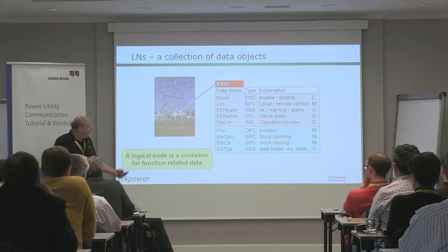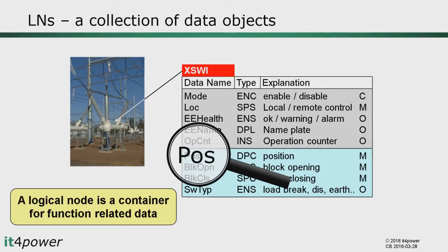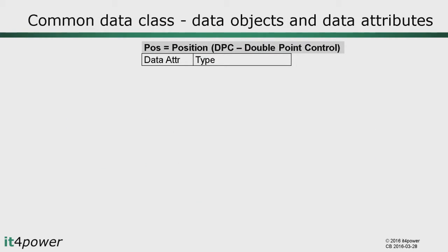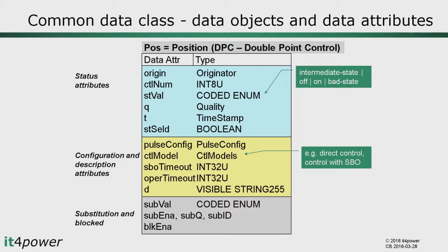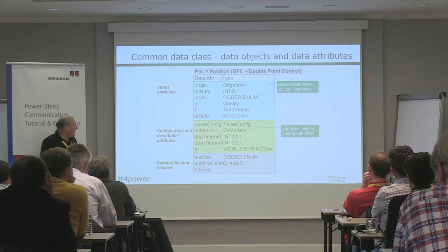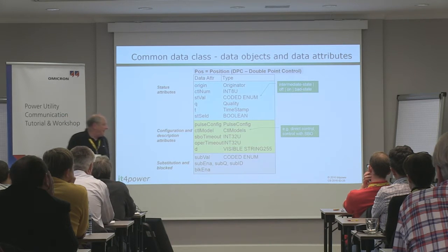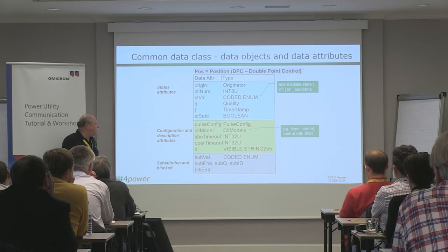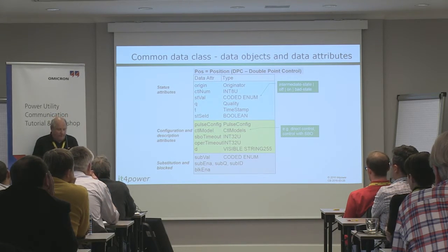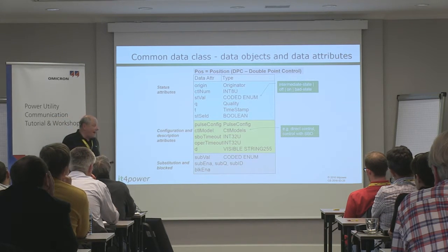Looking in more detail at the position data object, the common data class 'double point controllable' defines a series of attributes: operational attributes representing the status value, quality, and timestamp, plus configuration and description information. For example, you can configure select-before-operate, and the class includes an attribute defining the timeout parameter for that operation. So the data object groups not only operational information but also configuration-specific information — all defined in the common data classes in part 7.3.